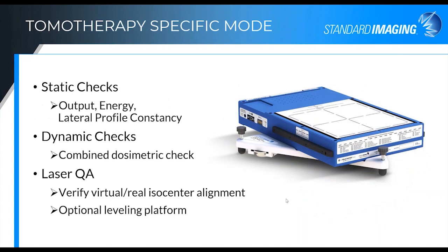And then just very briefly, a little bit more on the tomotherapy specific mode here. It comes along with, in that case, a leveling plate where you would align it, and first you would level the surface of the device using the included level and the 3 position adjustable screws on this platform. You'd align it at isocenter.